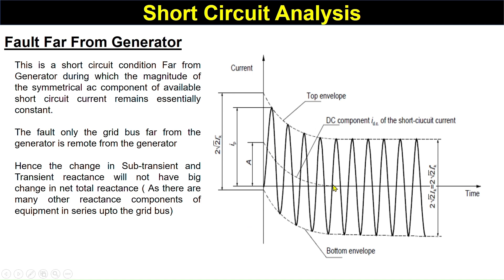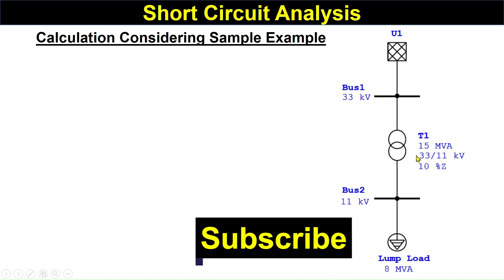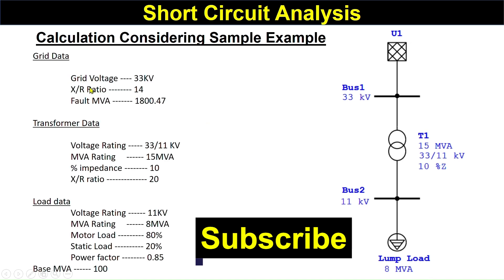Now we will take a simple example. Here is a grid with a 33 kV bus and an 11 kV bus, with a transformer of 15 MVA, 33/11 kV, and 10% impedance, and a lumped load of 8 MVA. The data you need includes: grid data (voltage 33 kV, X/R ratio, fault MVA), transformer data (voltage rating, MVA rating, percentage impedance, X/R ratio), and load data (voltage rating, MVA rating, motor/static load, power factor, and base MVA).